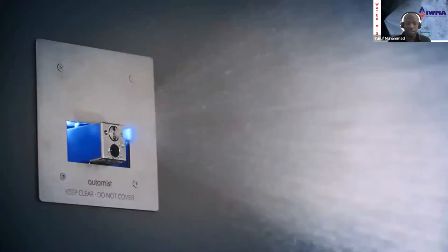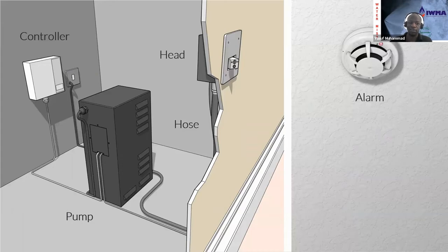Okay, so to explain, so you can get your head around the way in which our system is put together, we have a controller, which is a computer, the brain of the system. That is connected to a pump. This pump is quite small. It's about the same size as a kitchen kettle. And from there, you would connect it to your existing water main. So no need for a tank. In the vast majority of installations, you can run off the existing water supply because it uses less water than a power shower. And then from there, you would run your high pressure hose to up to 6 heads uniformly distributed throughout the property. And as I said before, a key part to this is the integration of the detection. So you can send a message if the system is activated or if there's smoke or heat building up within the premises.